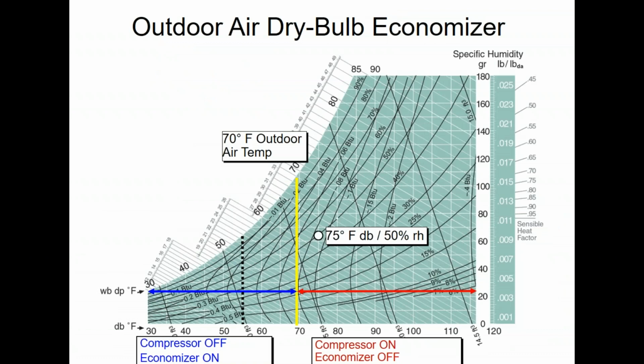So if we plot that out, instead of that black dotted line at 55 for our traditional set point for outside air changeover, the line moves over to the yellow area over there. Right? So what that essentially means is that this is an economizer day, this is a compression day, this is now also going to be an economizer day. So I got to accept air that's 60, 65, 70 degrees outside air temperature as free cooling air. Now, you're probably smart enough to realize we can't cool the space with 69-degree air. However, 69-degree outside air is probably cooler than whatever our return air is. So it's an improvement from that.